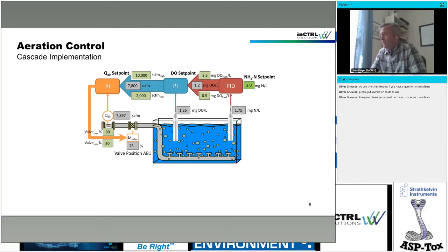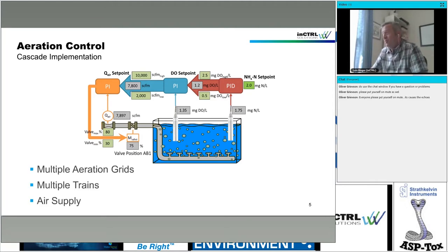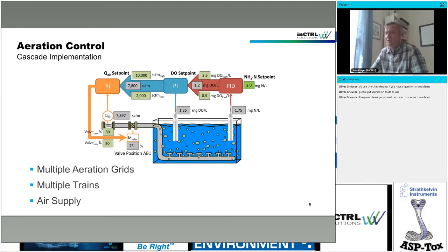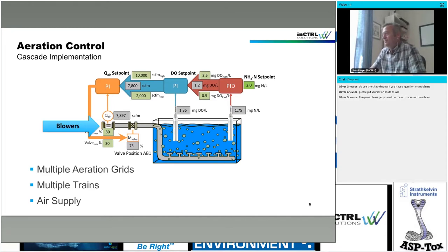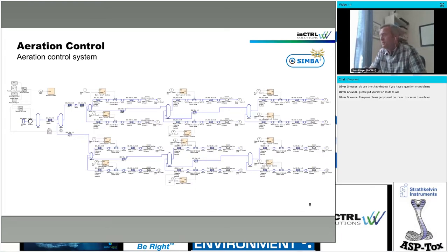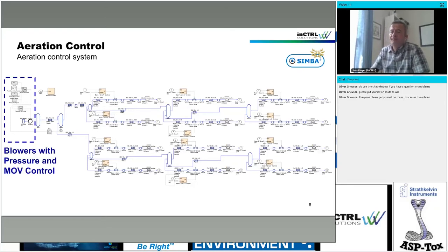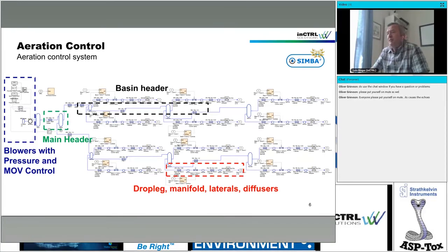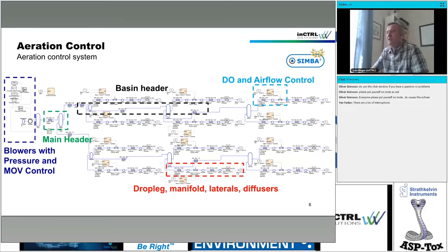To make it even more complex, this is just one control loop or one controller. If you have multiple controlled aeration grids, this doubles or triples the number of controls. You may have multiple trains, and keep in mind that is all only air distribution control — you also have the air supply control, or in other words, the blower controls. So it becomes quite complex, and the way we deal with that complexity is to put all of that into a model, modeling everything from the blowers, blower control, maybe most-open-valve control, the main headers, basin headers, droplegs, manifolds, laterals, up to the diffusers — which is the connection with the process — and then the DO and air flow control.